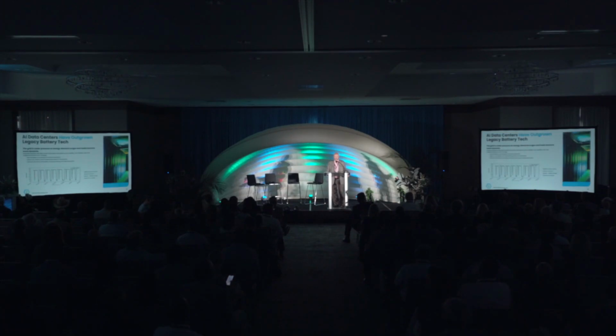Looking at this slide, this is a picture of a small data center load—one of the early AI data centers. It's about 160 megawatts, and the power's gone up and down 40 or 50%. So with an AI data center, you're seeing hundreds of megawatts jumping up and down 10, 12, 14, 15 times a minute. You can't connect that to the grid without causing problems—you'll start tripping substations, houses, subdivisions, towns. And those are issues which have to be managed.